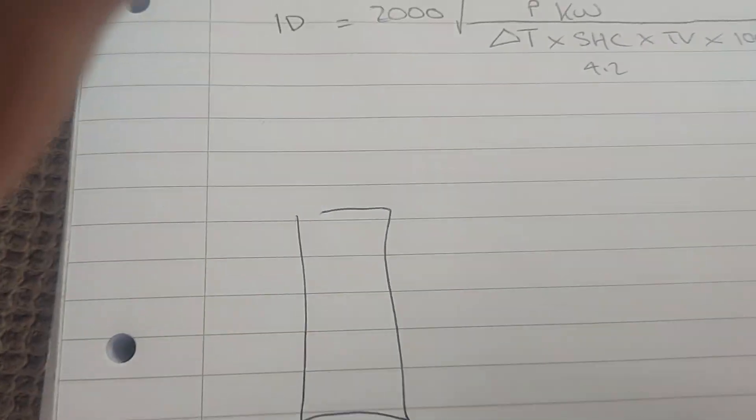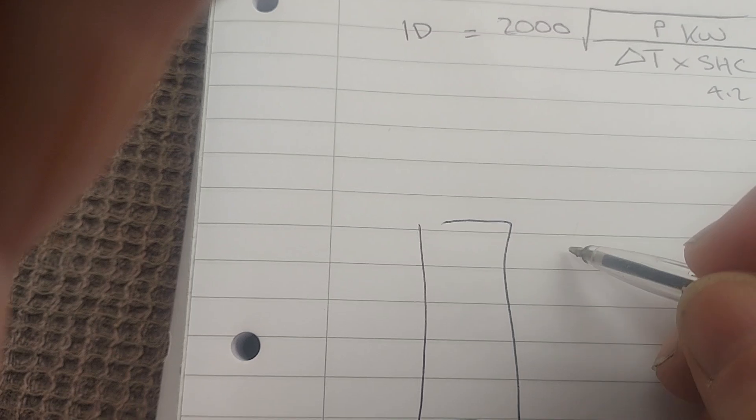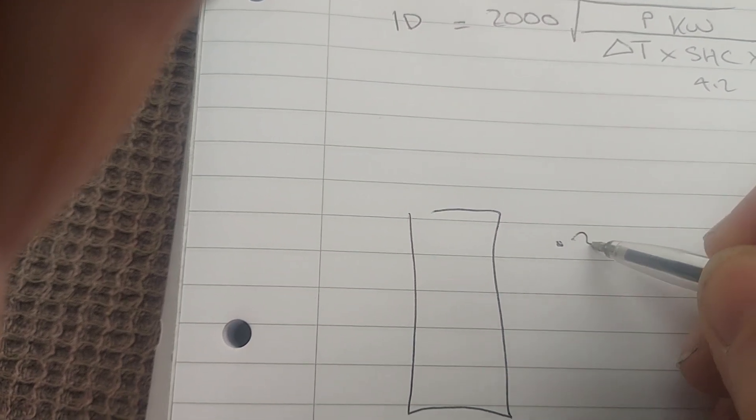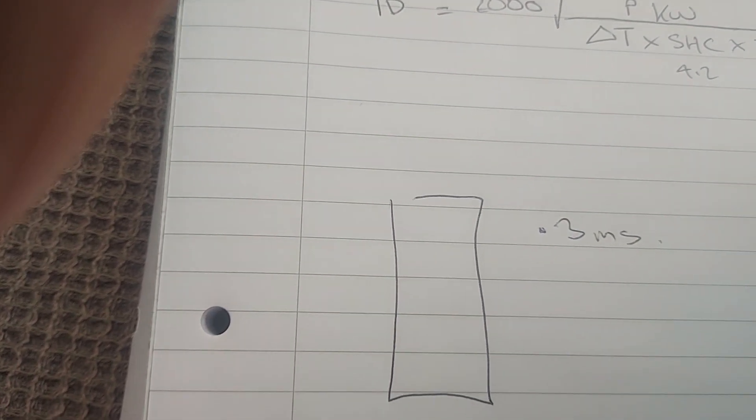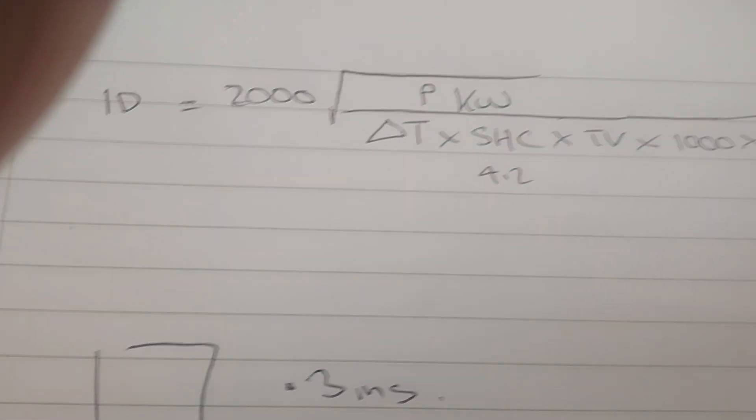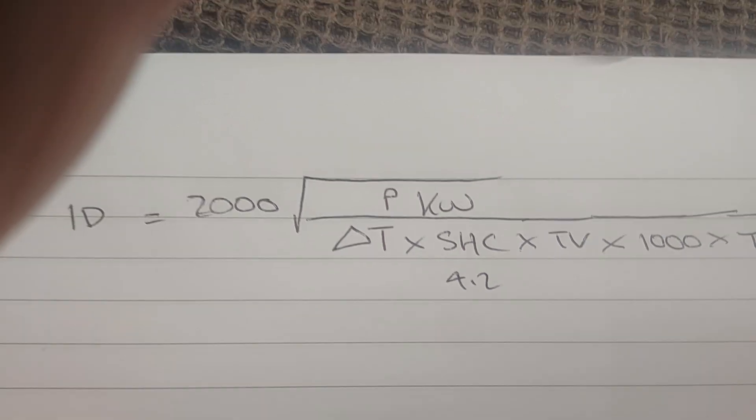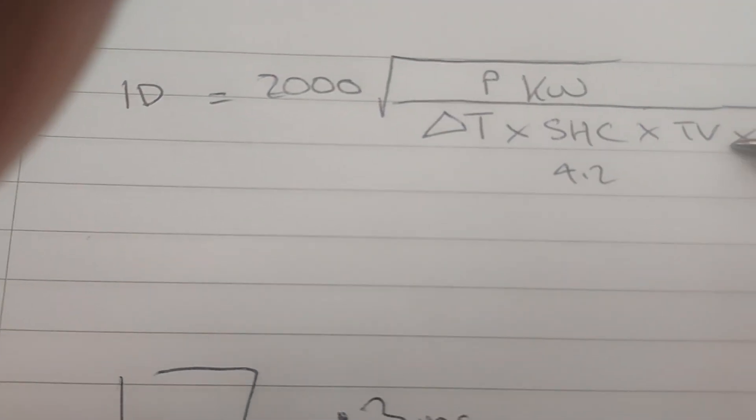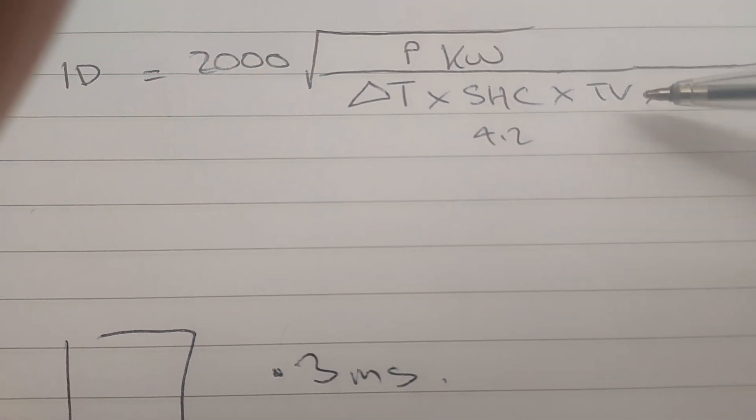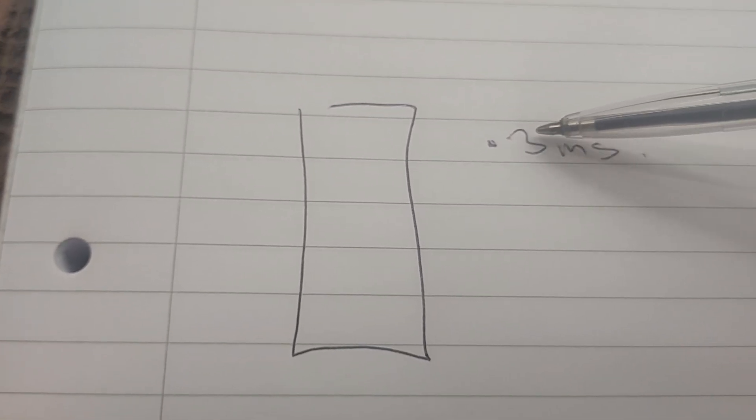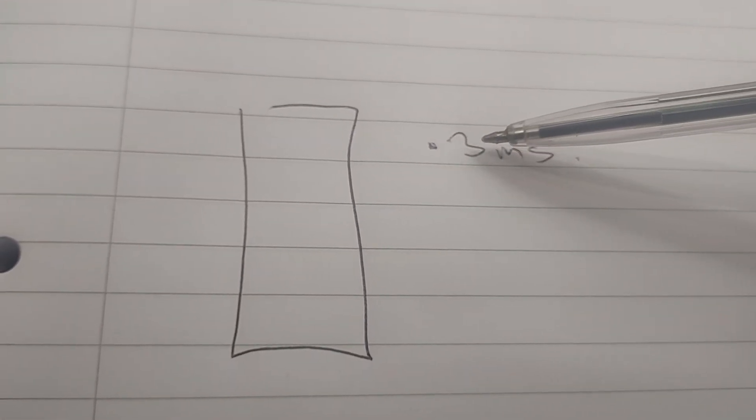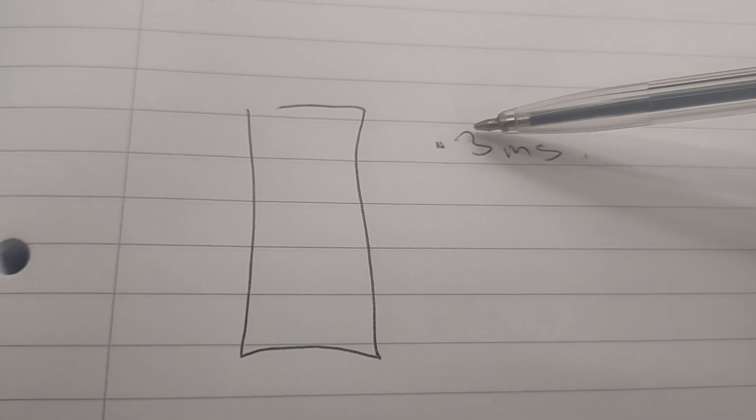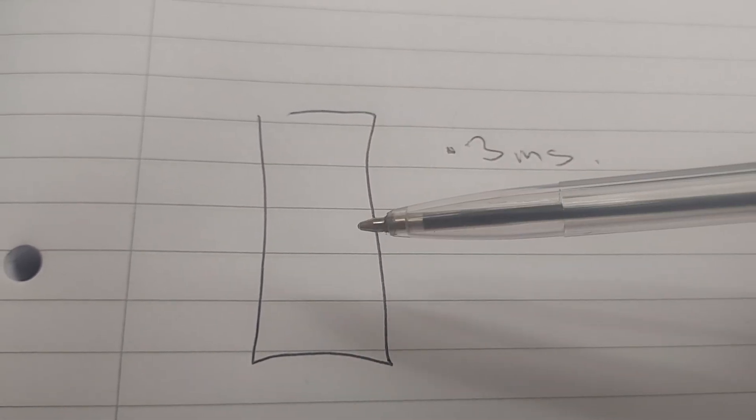If you were sizing a low loss header, we have a target velocity for a low loss header of 0.3 meters per second. So our target velocity value in our formula here will be 0.3 meters per second. Now I think on Kim Betty's course he teaches 0.1 meters per second.